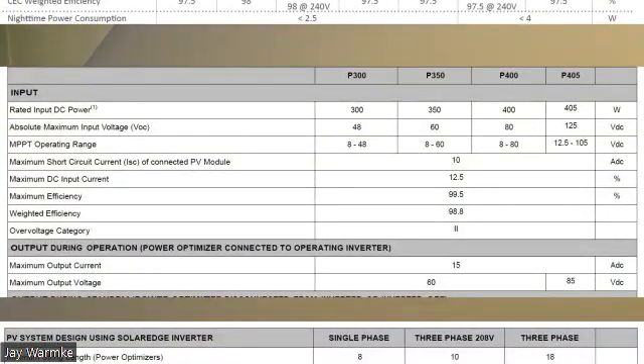So what happens is the optimizers adjust the amperage so that they keep the voltage, in this case, at 350 volts. But it's got to be 350 volts when it reaches the inverter, not 350 volts when it leaves the optimizer. So if I had, say, 15 volts of voltage drop between the optimizer and the inverter, then that optimizer would be generating at 365, and then it's received at the inverter at 350. So that's an important thing to remember.